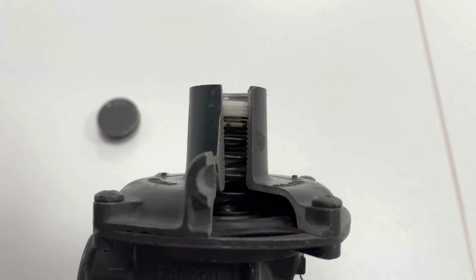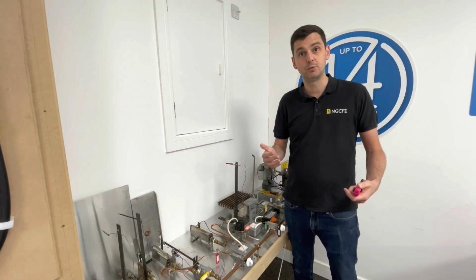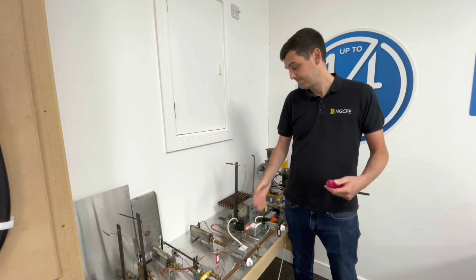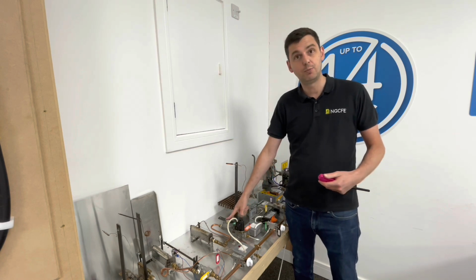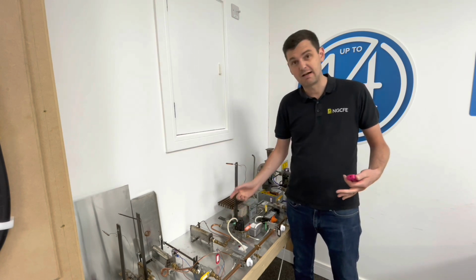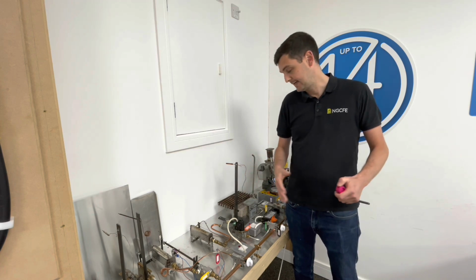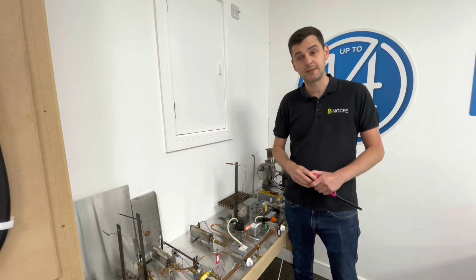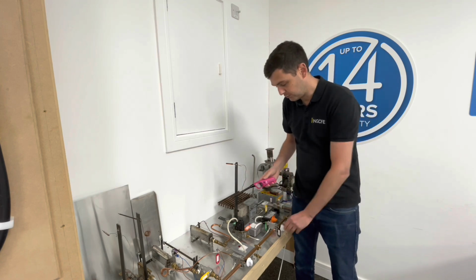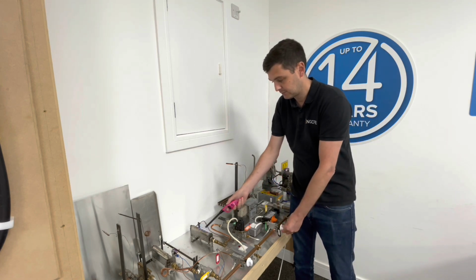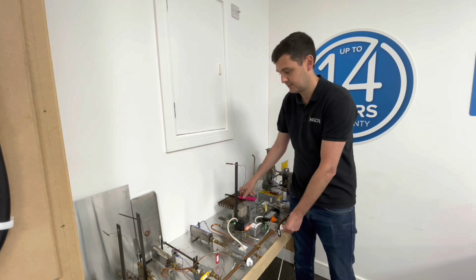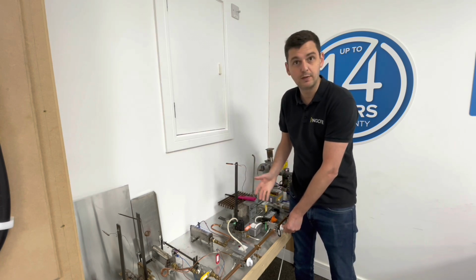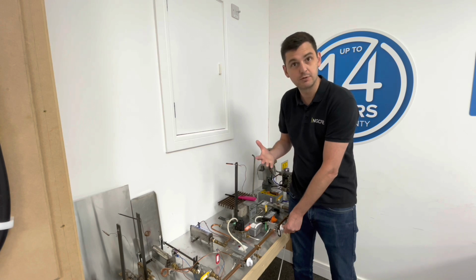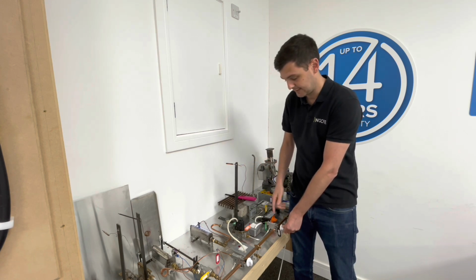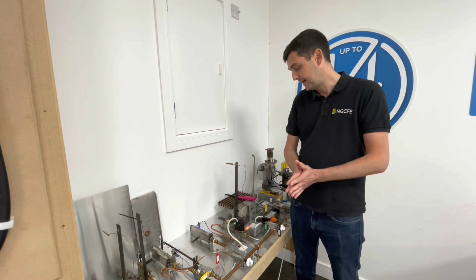On a typical gas meter in a property, that outlet pressure will be 21 millibar plus or minus 2. On this low pressure regulator, for example, it's around about 6 to 10 millibar, depending on how we set it. You can adjust it. So if I allow gas through, light the burner, again we've got a thermocouple there that's heating up. Once that heats up to a sufficient temperature and produces enough current, it will then hold this valve open. Now, how can we test these two controls?